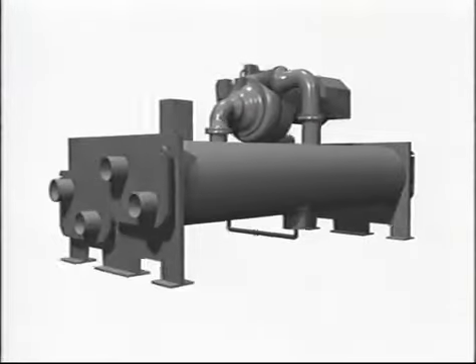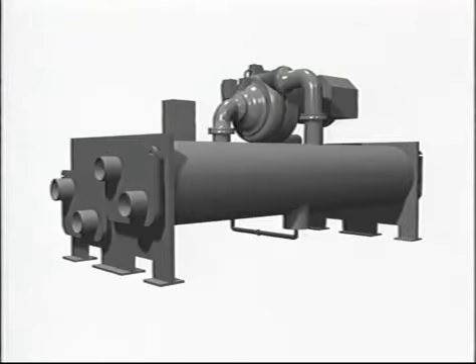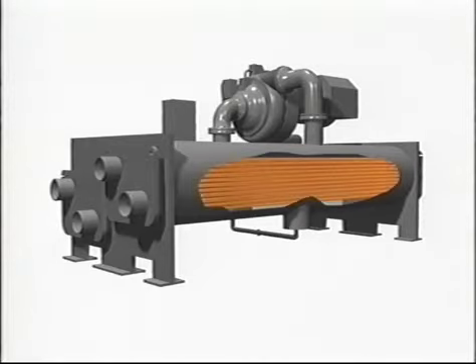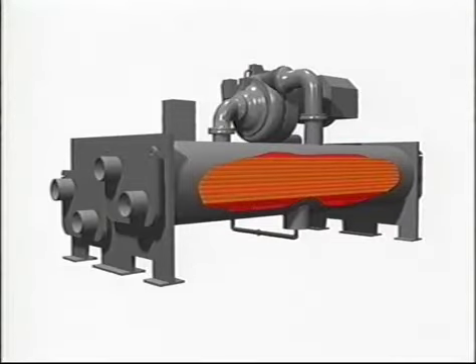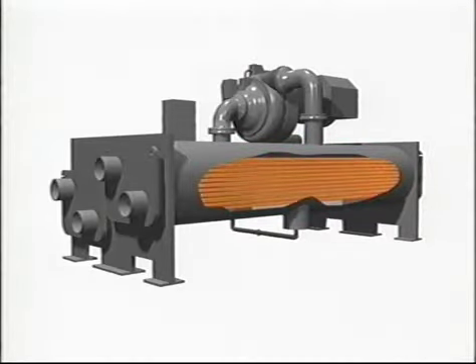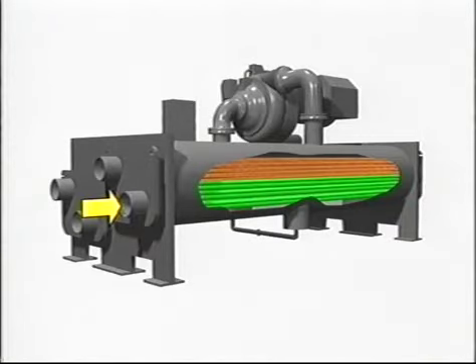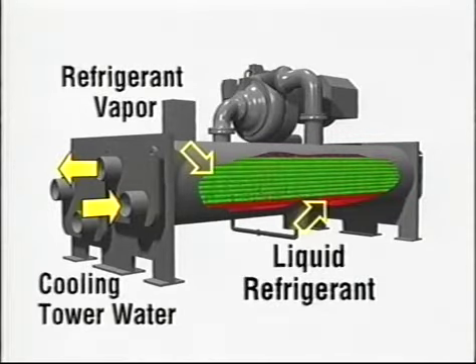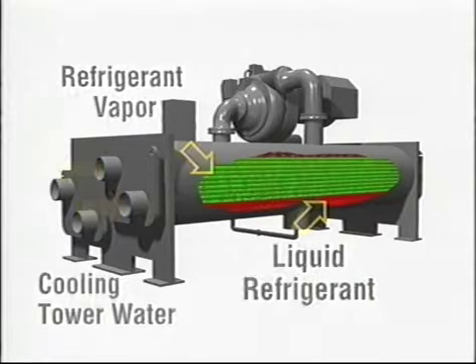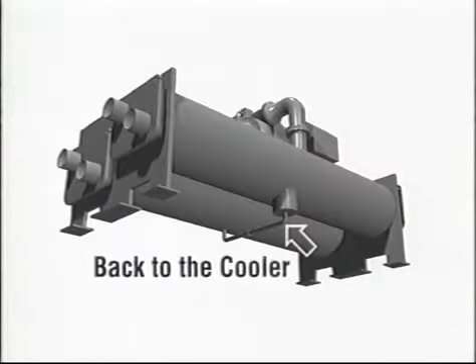Now, the heat that passed from the building to the water and into the refrigerant must be removed, and that happens in the condenser. The condenser is another big tank with tubes running through it. Like the cooler, the refrigerant is on the outside of the tubes, and the cool condenser water runs through the tubes. The condenser water absorbs heat from the refrigerant and then circulates to a cooling tower, usually on the roof of the building, where it rejects the heat to the atmosphere. As the refrigerant is cooled, it condenses from a hot gas to a warm liquid, which is then fed to the cooler to repeat the whole process.